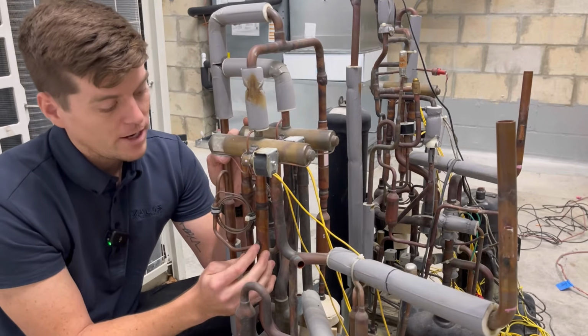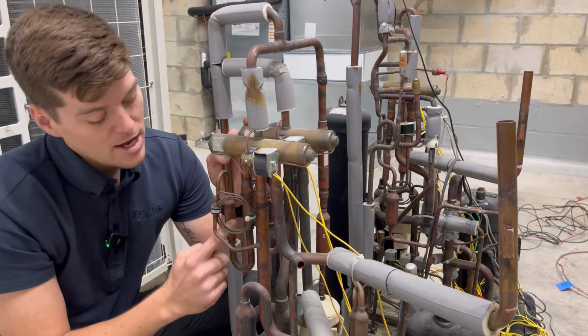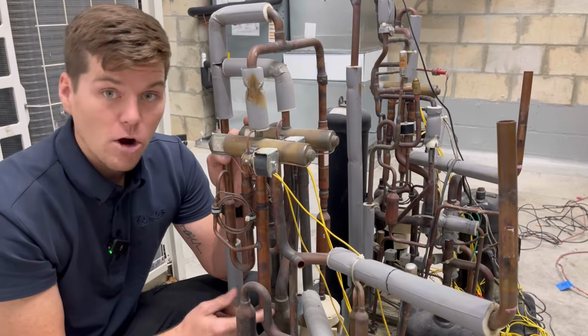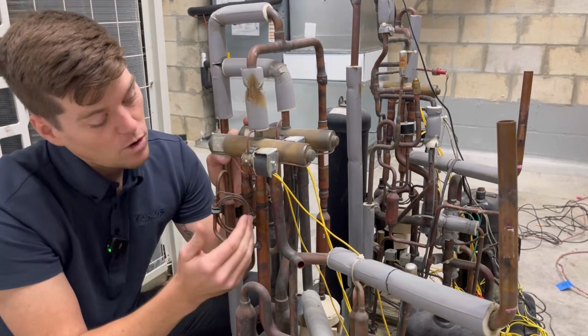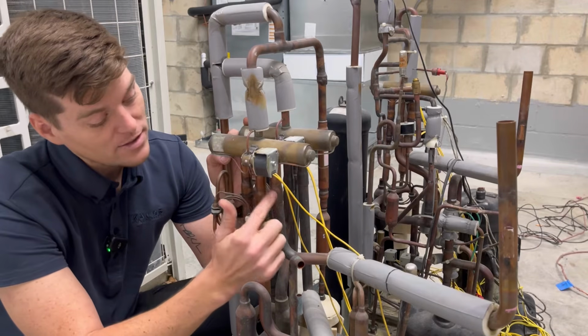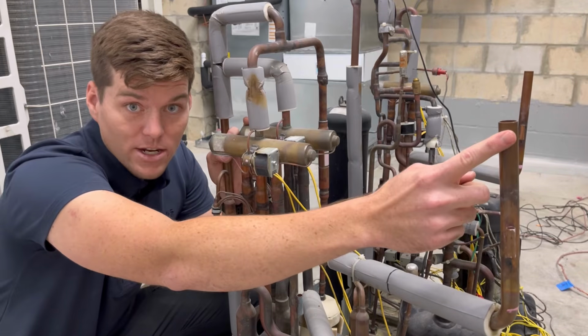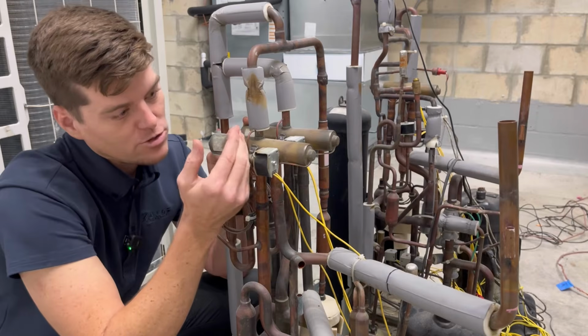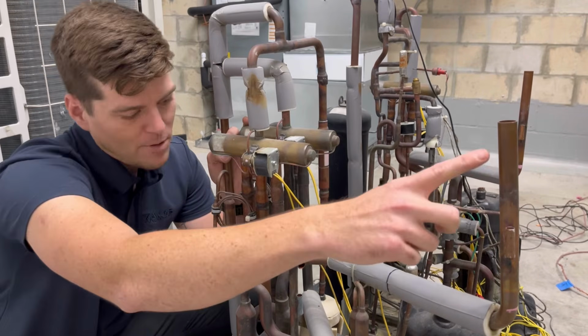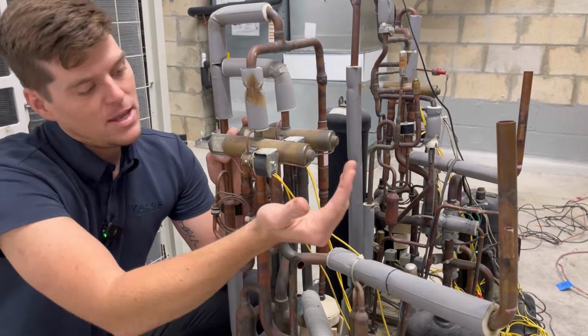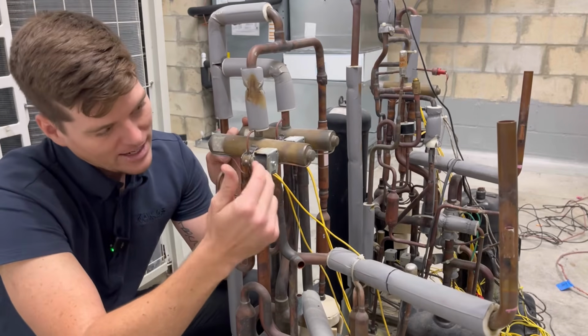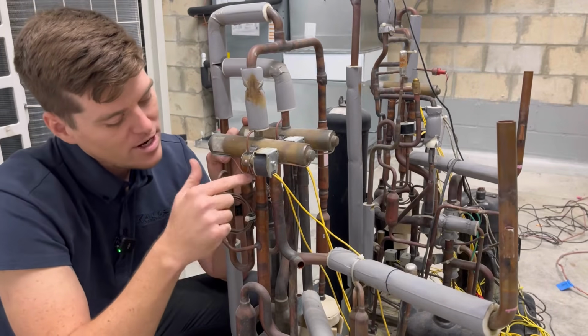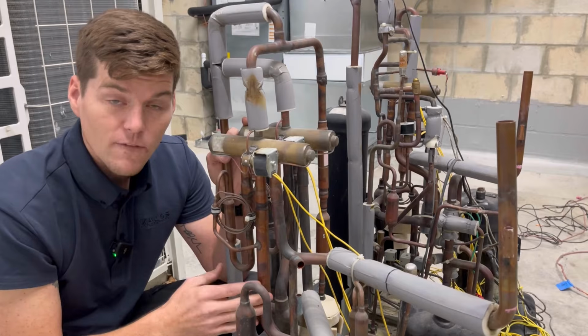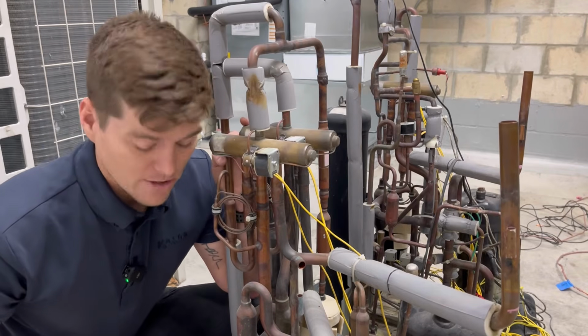It's the reference tube on here. You notice that if it's shifted here to the left, it's going to this dead head here, which bleeds back over into the suction line, right? And if it's shifted over to the right here, then it's connecting these two pipes here, which goes to our outdoor heat exchanger, right? That would be in an evaporative state. So it would be shifted over here if it's in an evaporative state, connecting it to the suction line. If shifted over here, it's sending hot gas up and over to the outdoor heat exchanger, deadheading the suction right back to itself. Now you're asking, well, how the heck do I determine that?